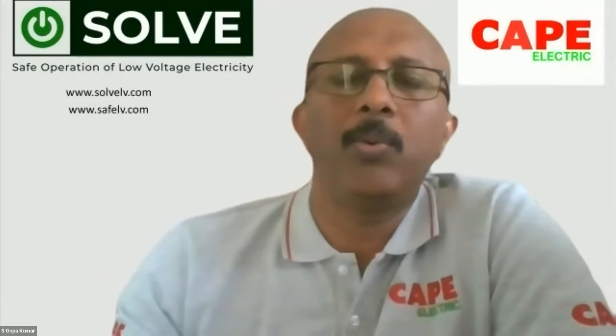Over voltage or over current, it will work, but not for instantaneous current. Similar is the situation with earth fault. Instantaneous tripping of the MCB may not happen. So such challenges also we need to handle. So periodic verification is very much necessary.